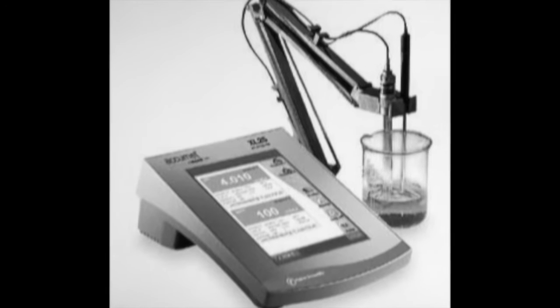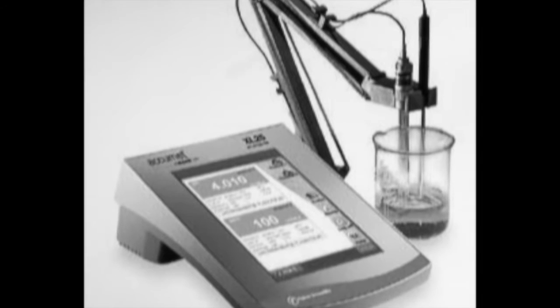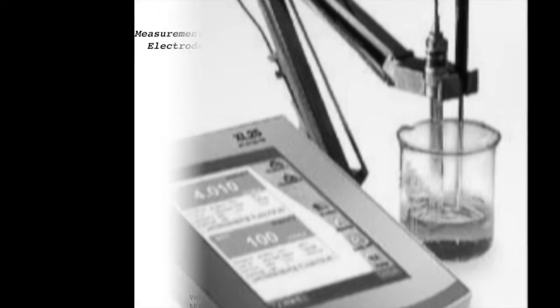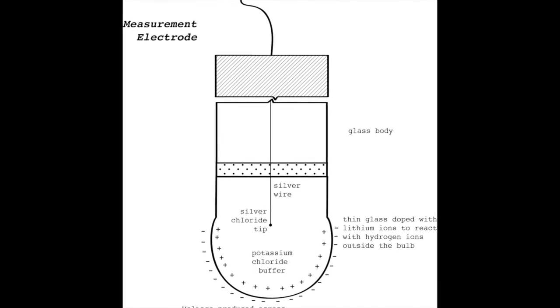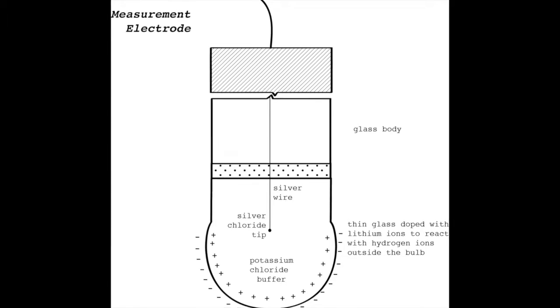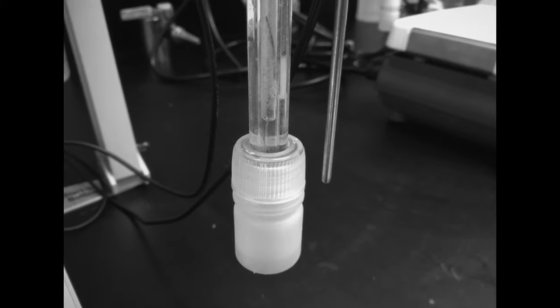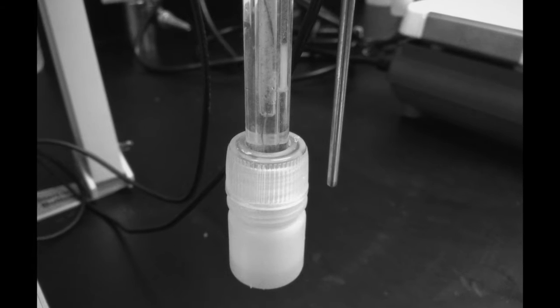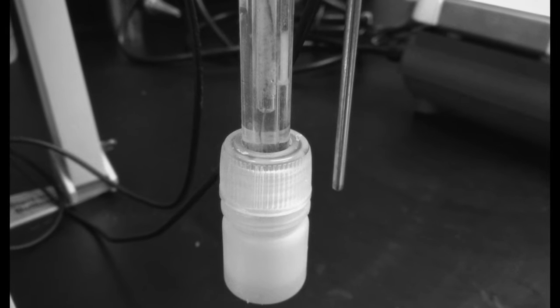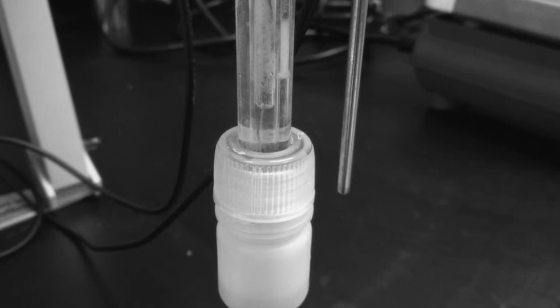Scientists have cracked the case with the Accumet XL25, a space-age device that gives spot-on numbers at the touch of a button, measuring the difference between the electrical potential inside and outside of the probe, which creates an electromotive force linear to the pH. The glass electrode is filled with potassium chloride to initiate an ion exchange with the hydronium ions in the solution. The technician rinses the probe with distilled water and dips the probe into the solution.